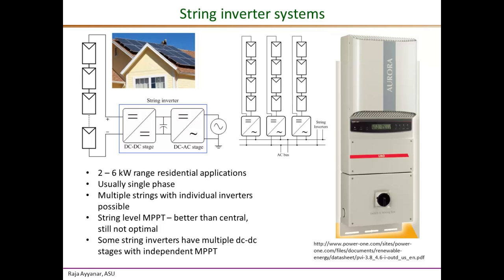Many string inverters now have a multiple DC-DC stage, offering multiple independent MPPT channels. For example, if you have two strings facing different directions on the rooftop — one east-facing and one west-facing — you can connect each string to independent channels of the inverter and have the advantage of independent maximum power tracking for each of those two strings.